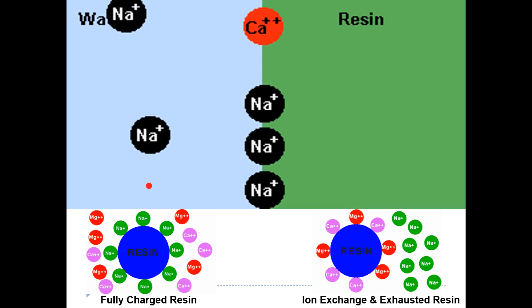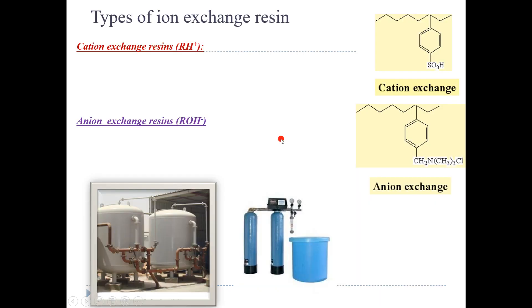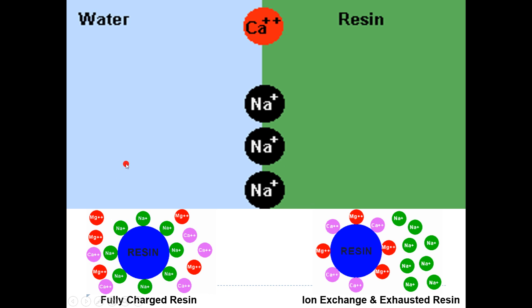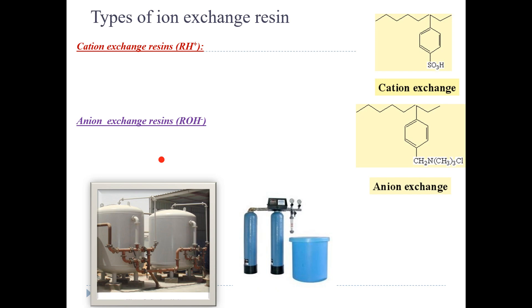There are two types — cation and anion — so we need two types of resins. Hard water contains calcium and magnesium ions, and the resin is made up of sodium ions. The exchange takes place such that a Ca2+ ion replaces two sodium ions. For Al3+, three sodium ions would be replaced. Hard water cations stay on the resin, and the soft water cations get into the water — so hard water is converted to soft water.